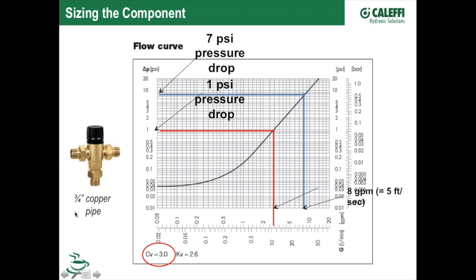The other thing that you have to be concerned about is the flow rate going through the pipe that you're going to connect this to. So if we've got 3/4 copper pipe, we want to stay under that 4 or 5 feet per second velocity going through that. So the limitation is not just the flow rate through the valve, but also the piping that you connect to it. So you can see as you go out on the hockey stick, up towards the handle of the stick, the higher up we go on these flow rates, the more pressure drop.